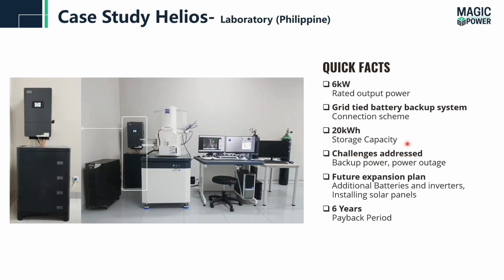Here is a case study for the Helios series low voltage energy storage system. There is a laboratory in the Philippines. Okay, they have installed a low voltage energy storage system. Here we can see the inverter and the batteries. There are four modules, and each module here is 5 kilowatt hours.